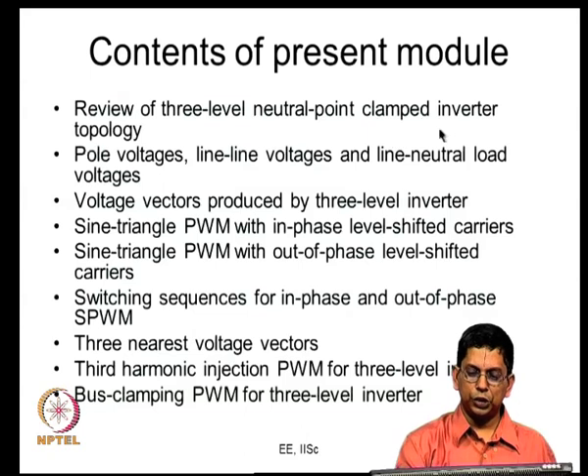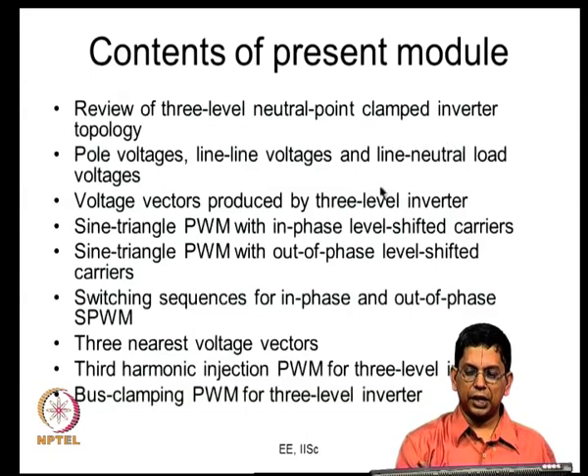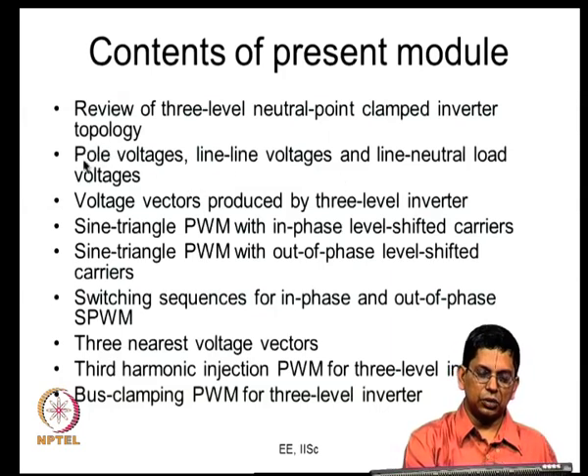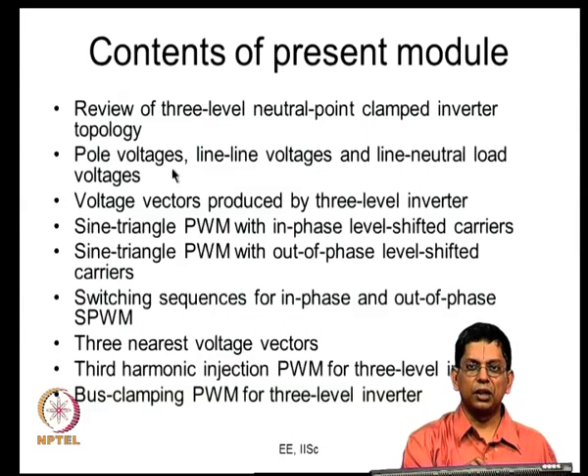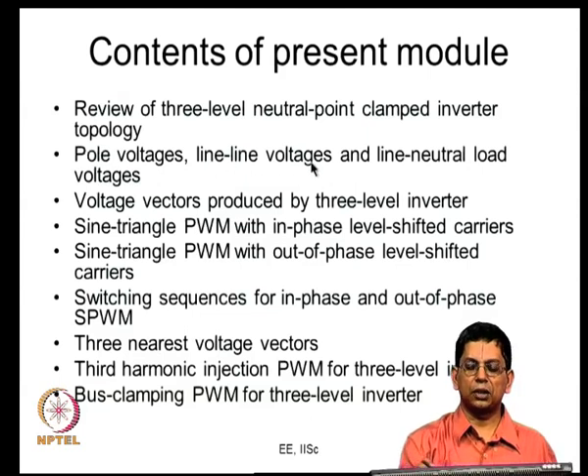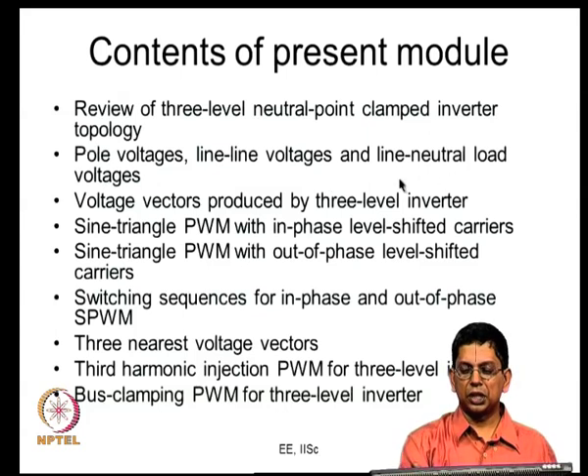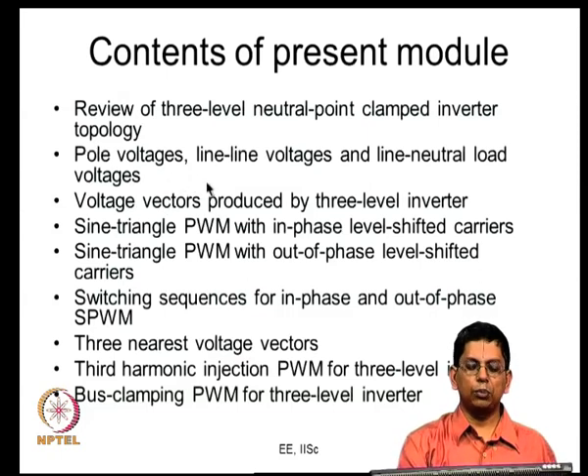In the present module we reviewed the neutral point clamped inverter topology and looked at pole voltages, line voltages, and line-to-neutral voltages. The essential difference is that in a two-level inverter the pole voltage can only be plus or minus Vdc/2, whereas here it can also be 0. This intermediate voltage level leads to more voltage levels — five different values for line-to-line voltage — and more instantaneous values for line-to-neutral voltage, which is responsible for improved waveform quality.